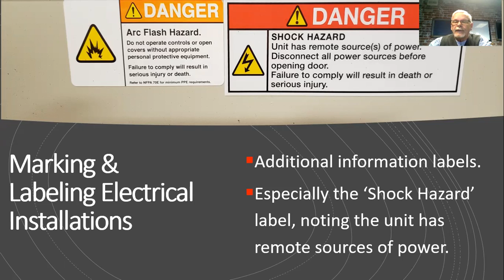One of the things that's kind of critical, and I have seen in multiple places, is equipment that's powered from remote sources. You have the local disconnect on the equipment itself, and you think that if you open that disconnect or turn it to the off position, your power is interrupted. But it's fed from another location as well. If that's the case, you need to have the additional label on. This label becomes very important, so nobody gets surprised.